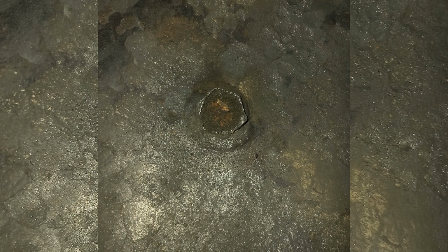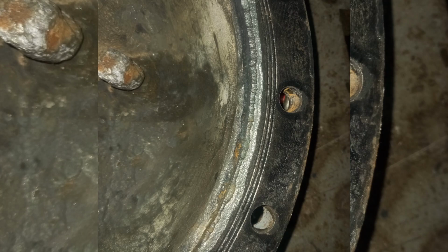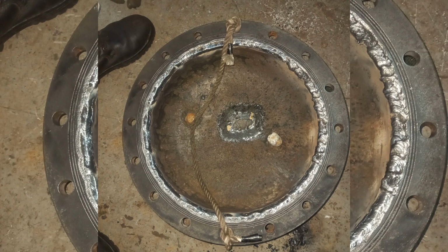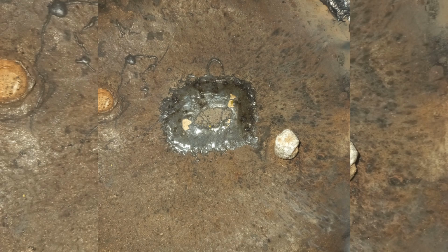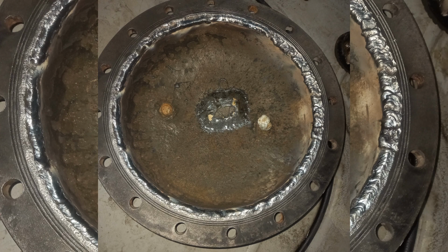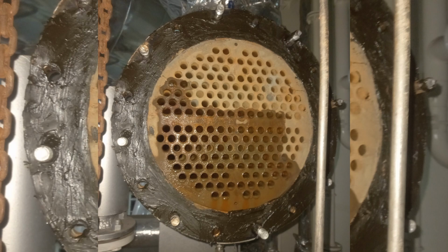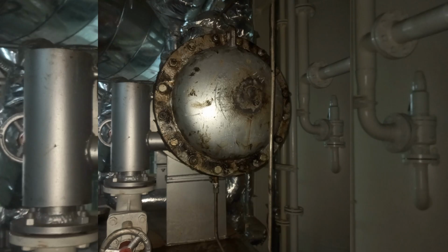Proper maintenance is very important to keep the condenser efficient, which includes regular inspection, leak checking, and especially tube cleaning, because dirt, scale, and rust deposits on tubes reduce heat transfer efficiency. Tube cleaning should normally be done once every 3 to 6 months, or more frequently depending on water quality and operating conditions.